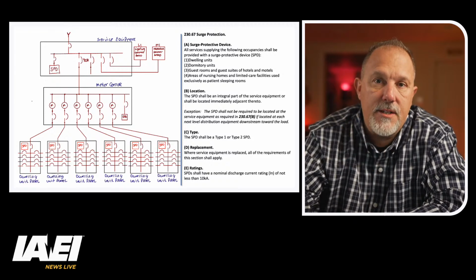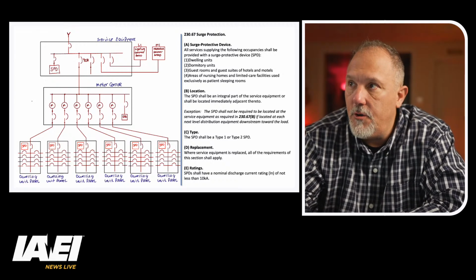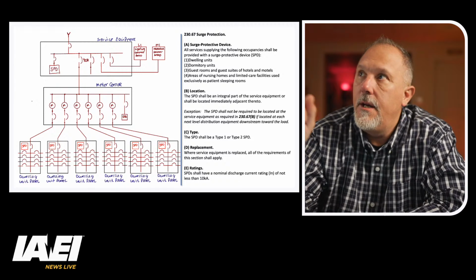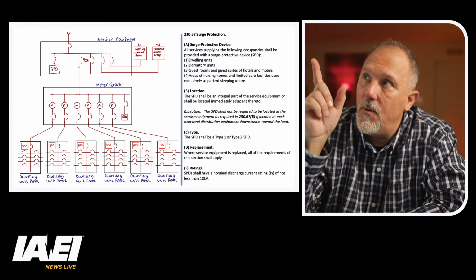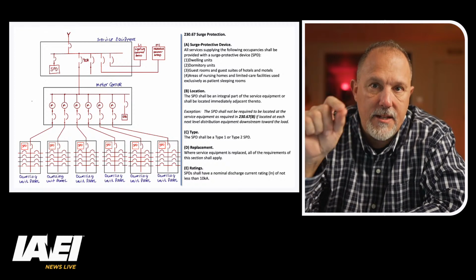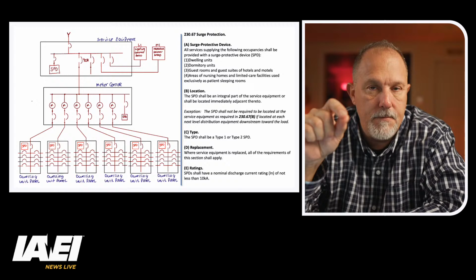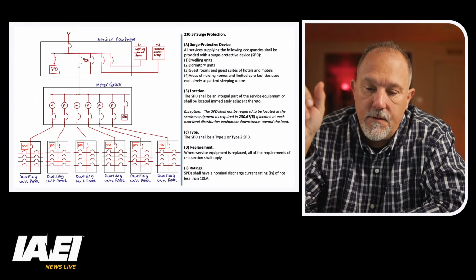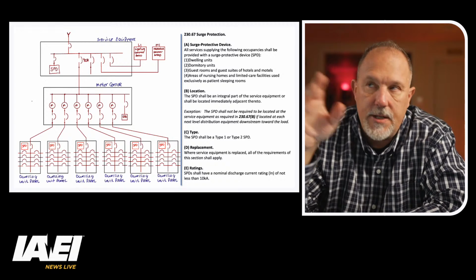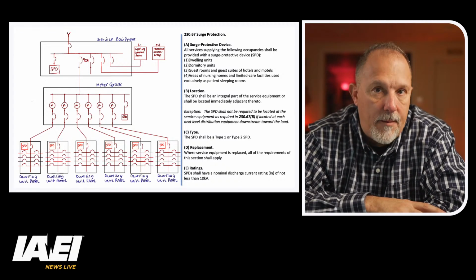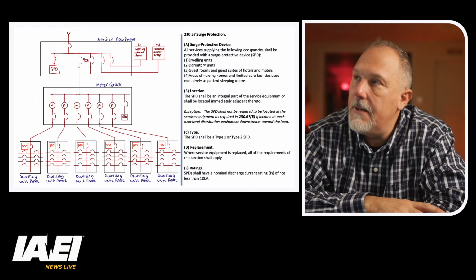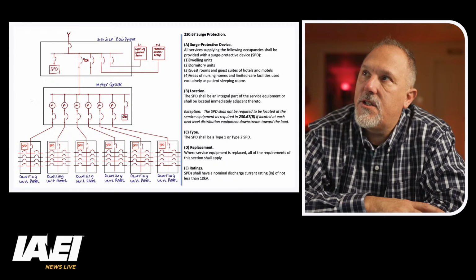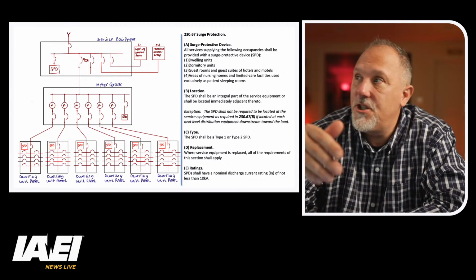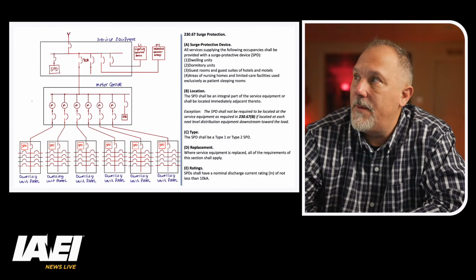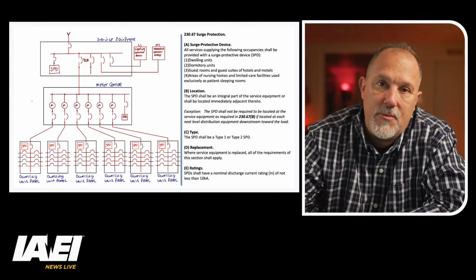Well, the meter center is downstream towards the load. The dwelling unit panel boards are downstream towards the load, but so is L1 and M1. Now, L1 and M1 was not supplied with a surge protective device because it wasn't required by code, because they didn't serve the dwelling unit, the dormitory unit, guest rooms, or guest suites. They supplied common areas for mechanical, HVAC, etc. So they didn't put a surge protective device in L1 and M1, and those two would be included at each next level distribution equipment downstream towards the load.